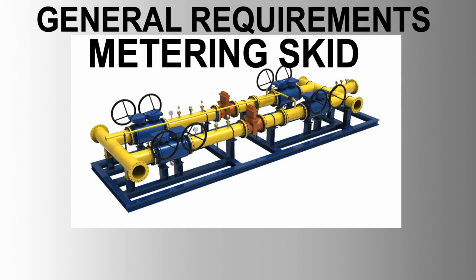6. Installation considerations. Straight length requirements. Upstream straight lengths for ultrasonic meters should be diameter dependent. USM DN 600 equals 40D, USM DN 500 equals 30D, USM DN 300 equals 23D. Flow conditioners can be used to reduce size and improve metering accuracy if validated by accepted practices or tests.